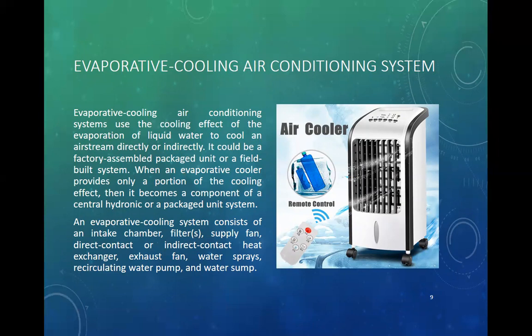It could be a factory-assembled package unit or a field-built system. When an evaporative cooler provides only a portion of the cooling effect, it becomes a component of a central hydronic or package unit system. An evaporative cooling system consists of an intake chamber, filters, supply fan, direct contact or indirect heat exchanger, exhaust fan, water sprays, circulating water pump, and water sump.